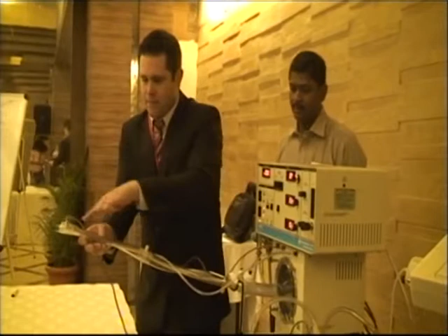What we have here is the ventilator column, this is the ventilator head, and really if you were to open this up, it looks like a radio speaker in there. So this is all contained within there. There's a cooling system that keeps the piston nice and cool, and that piston's going to beat back and forth. Well, there's a fresh gas that's going to come from the humidifier. We're always going to make sure the humidifier is on, right? So the fresh gas comes through the humidifier, goes into the inspiratory limb. This is your inspiratory limb right here. This is the temperature probe, right? And that gas is going to come through the system.